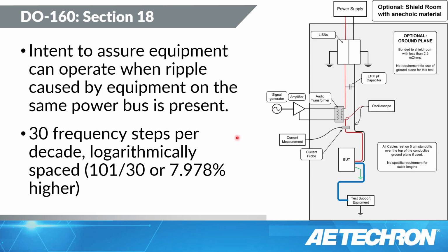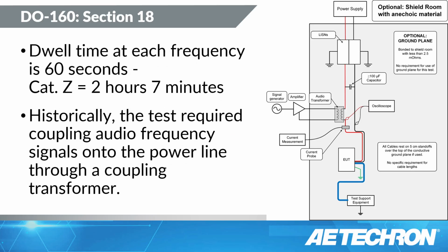Now let me go to the next slide here. So you're dwelling at each of these frequencies for 60 seconds. Now the test starts at something like 10 hertz and goes up to 150 kilohertz. Well, that test is going to require 2 hours and 7 minutes at 60 seconds at each specific frequency. And maybe longer if you have some settling and dwell times at each frequency. So historically, this testing has been very, very slow.